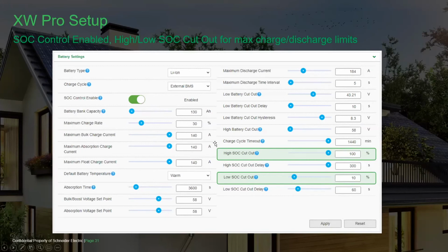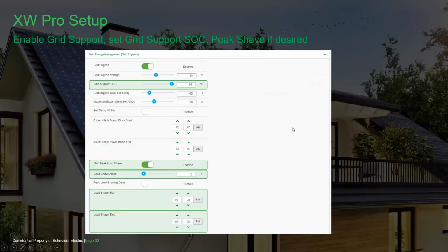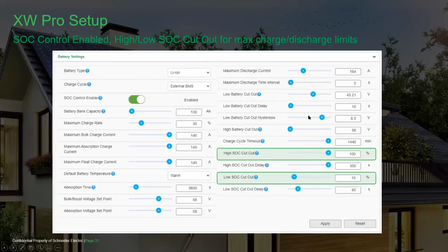Now, all of the voltage controls in the system, except for high battery cutout and low battery cutout, are irrelevant. So your low battery cutout is still respected, even though SOC control is enabled. So if you don't have these backed off out of the way, you could get some nuisance tripping. So I usually recommend going up to, say, 60 volts for lithium batteries. And the low battery cutout is dictated by the Discover battery.